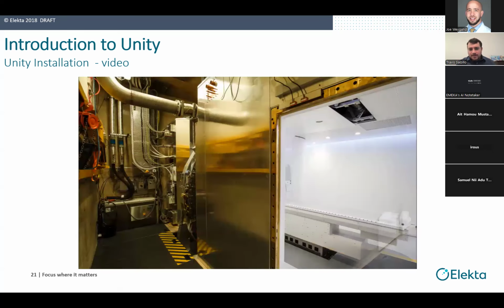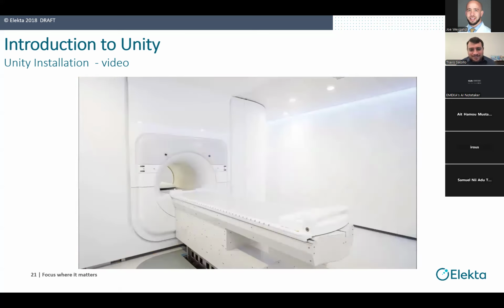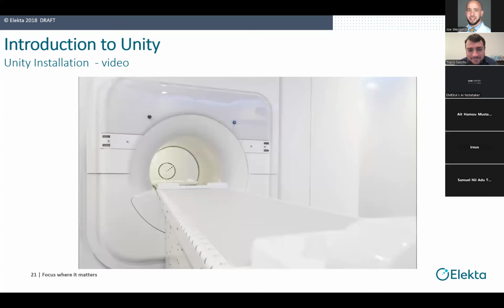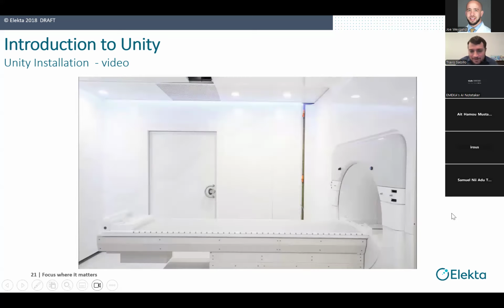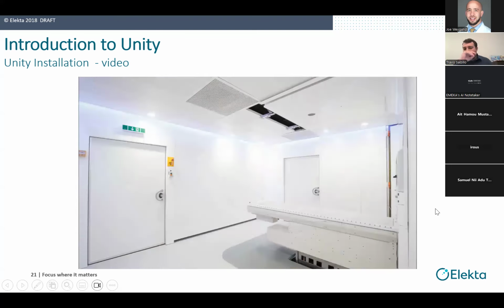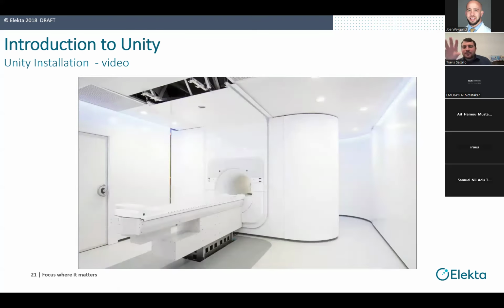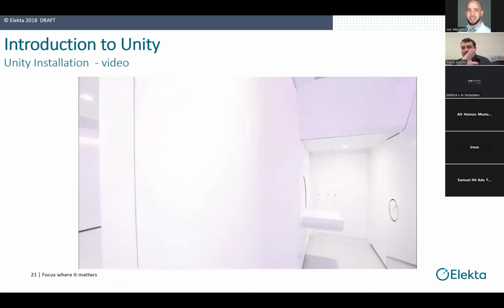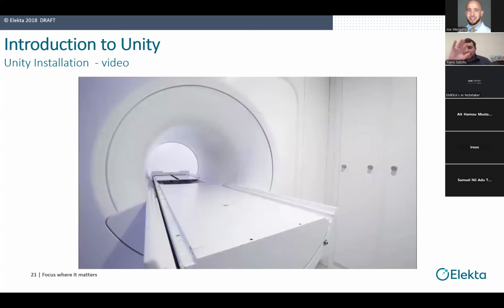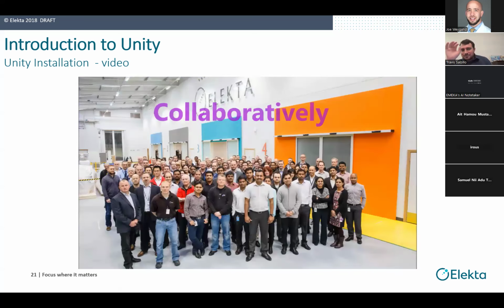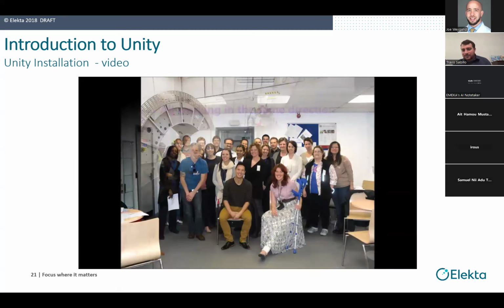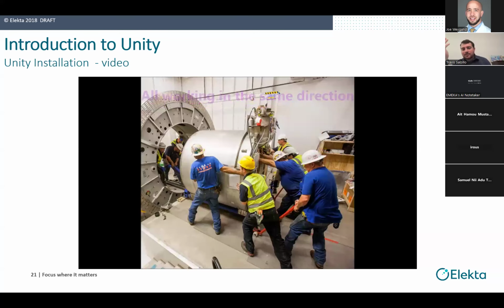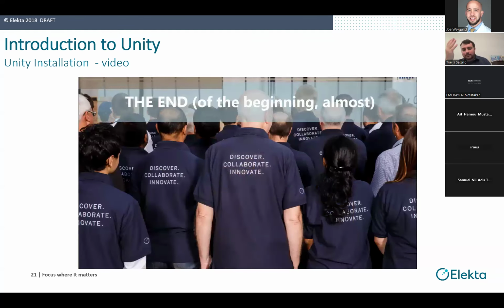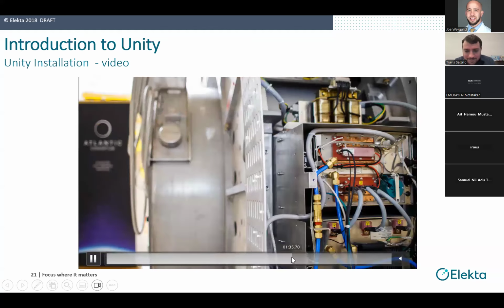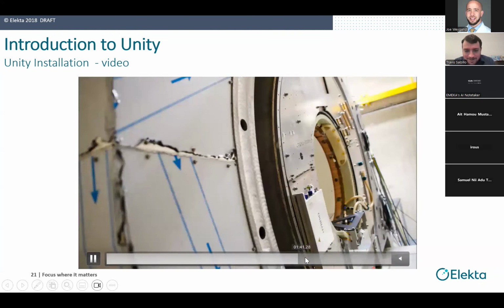So this is a modulator cabinet and a few other things. Yeah, they didn't really show the birdcage. Unfortunately, this is a finished product. I wonder if there's a way; I'll let it finish and see if we can identify the point at which you see it. But yeah, this is basically a room within a room. So this is a room that has a Faraday cage around it that keeps RF interference out. And then you can step out of this room into the vault itself, and that's where all your lead shielding is, your concrete shielding and your lead door, to obviously shield from the high field radiation.